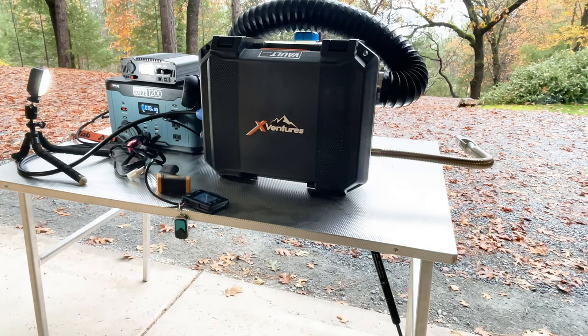Well, literally a few minutes after turning off the video, it's burning clean now. No smoke coming out of the exhaust. So total of maybe 25 minutes to expect oils and smoke to come off of the exhaust manifold. The unit itself, as you saw in startup, burned with smoke for only a few minutes. But for whatever reason, that exhaust manifold definitely has some oils in it. So right now it's burning absolutely clean.